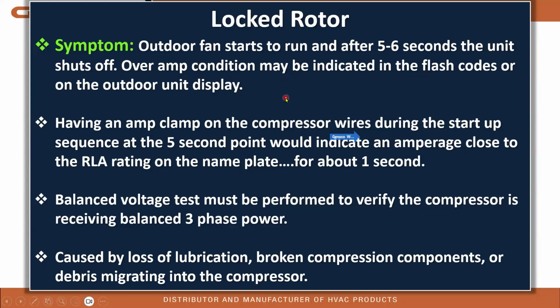Before condemning the compressor, you must perform a balanced voltage test to verify that the compressor is receiving balanced 3-phase power. After all, it is a 3-phase motor, and it requires 3 phases of power for it to actually turn. If you're only getting 2 of those phases, it's just going to sit there, locked rotor. The most common cause of a locked rotor is a loss of lubrication or a broken compression component, such as one of the scroll pieces has broken off and is now jamming the scroll section, or debris migrating into the compressor, preventing it from turning.